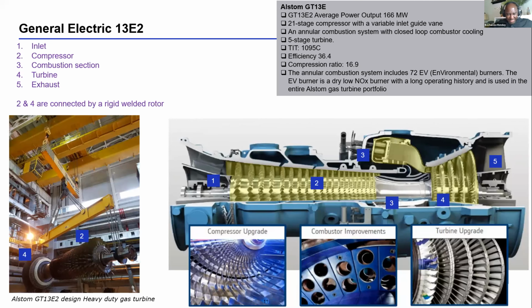So, maintenance of these gas turbines. GE has more series of maintenance. So they have the combustion chamber inspection, the hot gas inspection, the major inspection. This is also another reason for upgrade. Sometimes you want to upgrade because you don't want to have more maintenance. They call it TBO, time between outages. So you can change the material so that you don't need to open your machine after a long period of time, for instance, or change your parts after a long period of time.